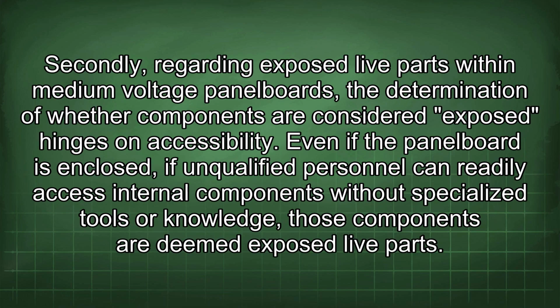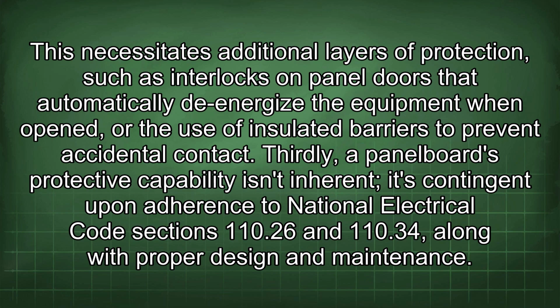Secondly, regarding exposed live parts within medium voltage panelboards, the determination of whether components are considered exposed hinges on accessibility. Even if the panelboard is enclosed, if unqualified personnel can readily access internal components without specialized tools or knowledge, those components are deemed exposed live parts. This necessitates additional layers of protection, such as interlocks on panel doors that automatically de-energize the equipment when opened, or the use of insulated barriers to prevent accidental contact.